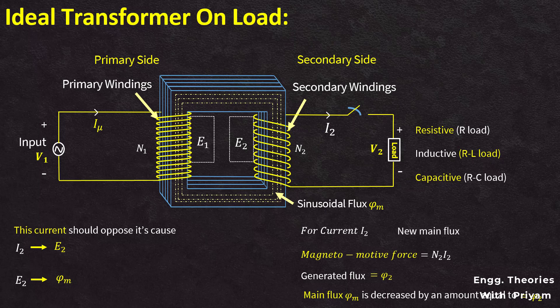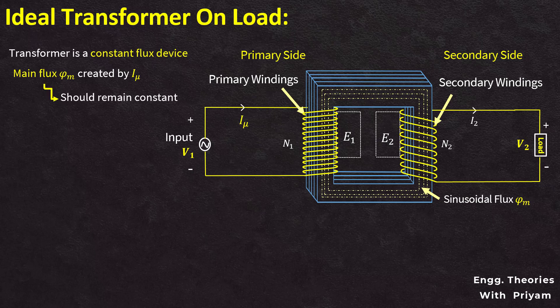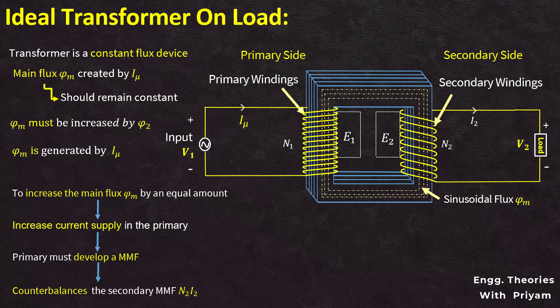So, our new main flux phi m prime is equal to phi m minus phi 2. Now, we know that a transformer is a constant flux device, that's why the main flux phi m generated due to the magnetizing current I mu should remain constant regardless of any change in the load. So, in order to keep this main flux phi m constant, we have to increase the flux phi m by an equal amount to the generated flux phi 2 due to the magnetomotive force N2I2. The main flux phi m is generated by the current flowing in the primary, which is previously equal to the magnetizing current I mu. In order to increase the main flux by an equal amount, we have to increase the current supply in the primary winding; in other words, the primary must develop the magnetomotive force which will exactly counterbalance the secondary magnetomotive force N2I2.